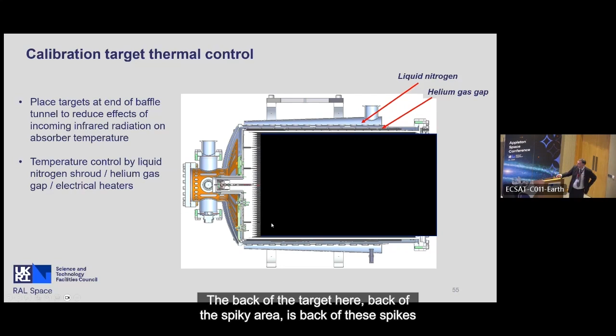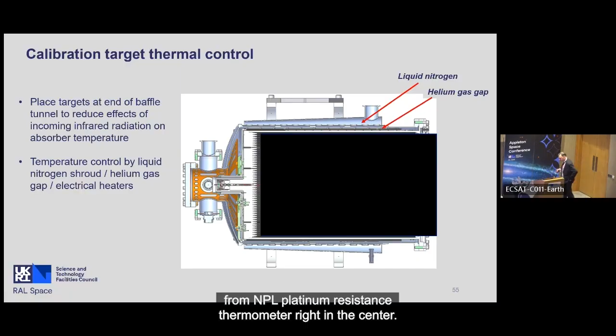If we want the target cold, we put a high pressure of helium. If we want the target warm, we evacuate the helium and use some foil heaters around the periphery, in a strategic manner, to up the temperature of the whole assembly. The back of the target, the back of these spikes here, is peppered with temperature sensors, and we have a calibrated from NPL platinum resistance thermometer right in the center.